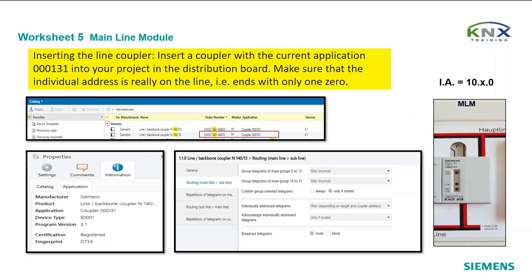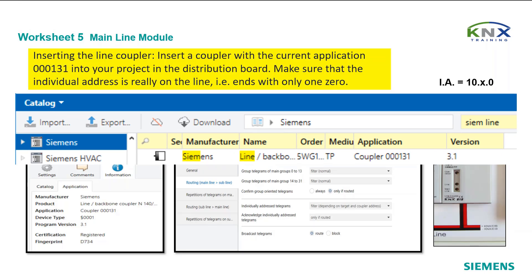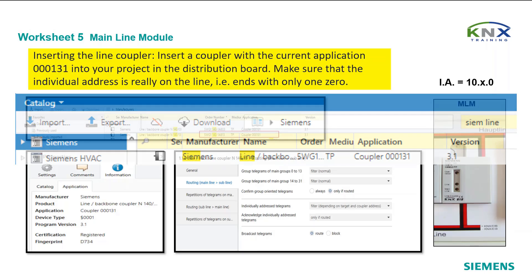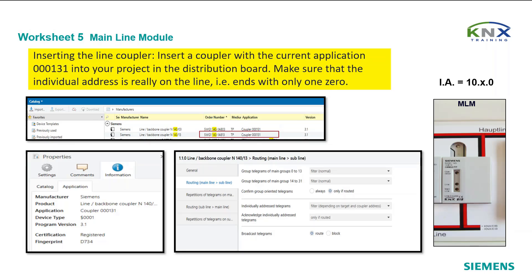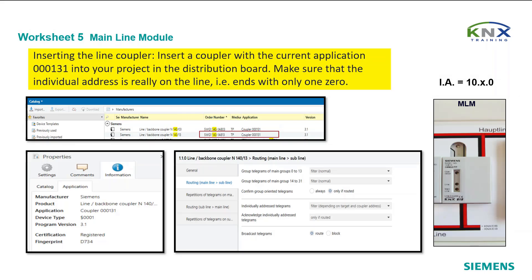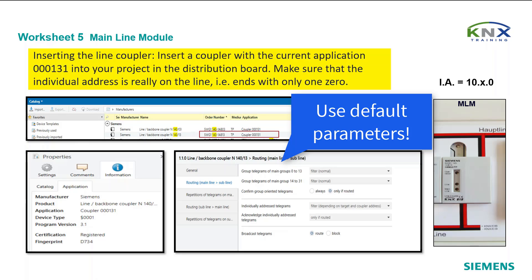Insert a coupler with the current application 000131 into your project in the distribution board. Make sure that the individual address is really on the line — that means it ends with only one zero, like 10.9.0. Leave all parameter settings unchanged; in the basic setting they work excellently. Changes should only be made if there are special requirements.